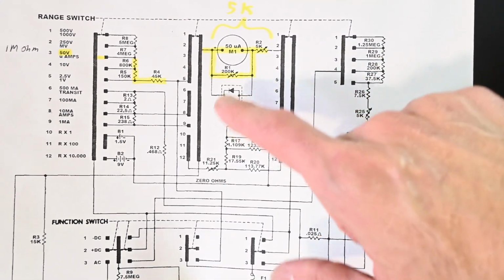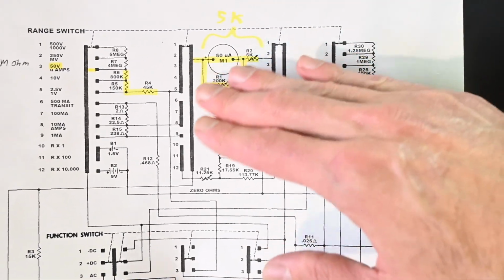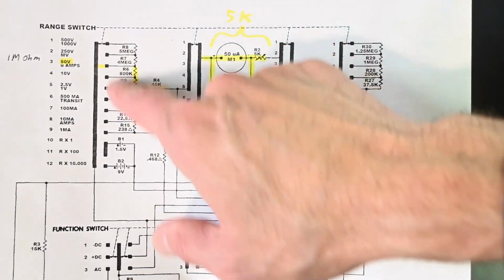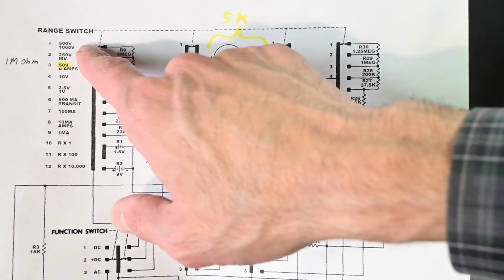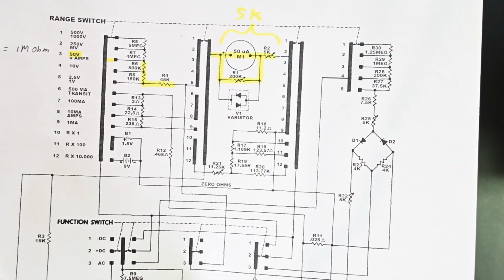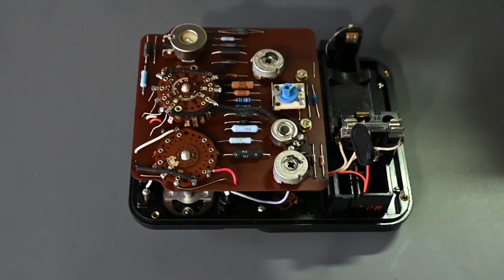And right now for this first procedure, first calibration, the range switch is just in the highest voltage setting over here, 500 volt, 1000 volt range. All right, so let me get things repositioned just a little bit so that you can see the Simpson 260 and the Keithley at the same time, and then we'll do the calibration.